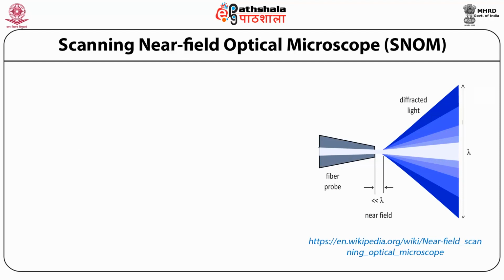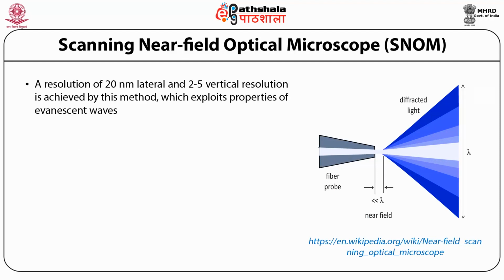This microscopy allows a very high resolution, 20 nanometer lateral as well as 2-5 vertical resolution. This is based upon the evanescence wave nature, and evanescence waves are actually oscillating magnetic fields which do not propagate. So if an evanescence wave is generated on the sample or within the sample, it will oscillate there, and the energy within that confined area can be used to generate a high resolution image of our sample.